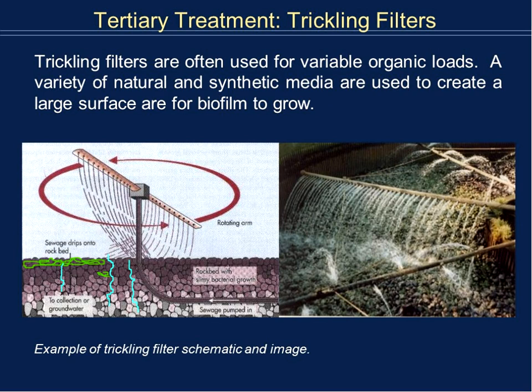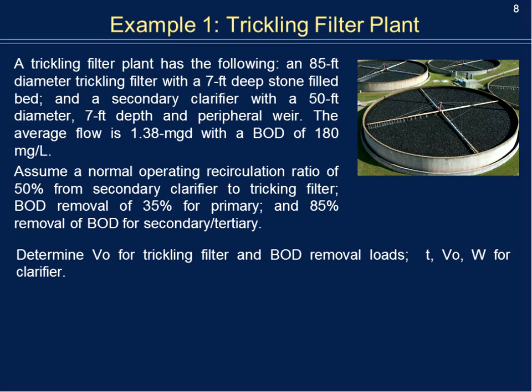The water trickles down to the bottom of the tank. At the bottom, there is a collection area which takes away the more clarified effluent and brings it to the final stages of treatment, which is often chlorination. For our example problem: we have a trickling filter plant with an 85-foot diameter trickling filter that is 7 feet deep, filled with stone. After that, there's a secondary clarifier — another settling tank — that is 50 feet in diameter and 7 feet deep.